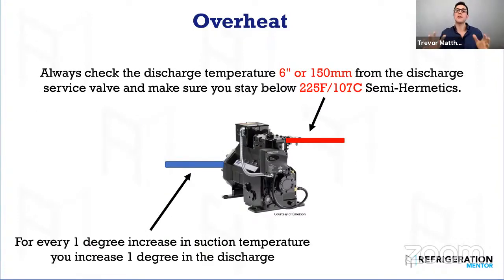Okay, always check your discharge line temperature. So many technicians do not do this. You need to check it 6 inches, 150 mm away, and you're looking for 225 as a good range. Compressors run at 225. It's usually lower than that depending on the application, but at 225 you're okay. When you start to get 300, 350 degrees Fahrenheit or 150 Celsius, you're starting to lose lubrication. And then you start to break down the oil, which causes major issues.